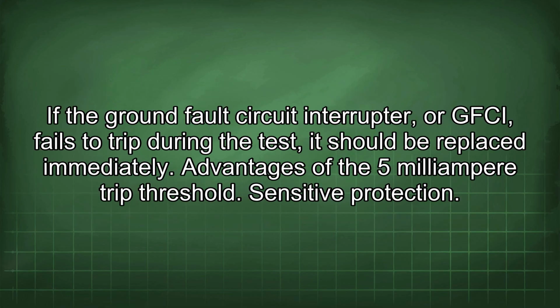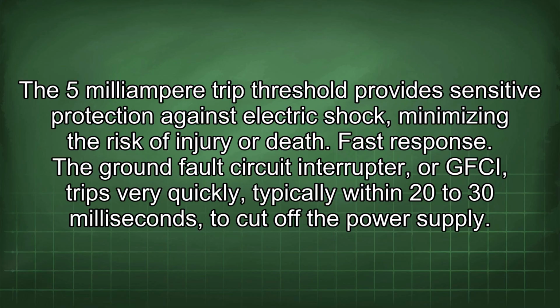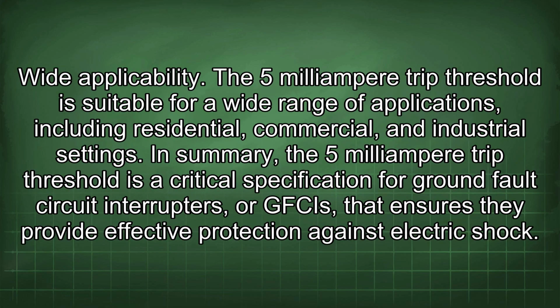If the ground fault circuit interrupter, or GFCI, fails to trip during the test, it should be replaced immediately. Advantages of the 5 mA trip threshold. Sensitive protection. The 5 mA trip threshold provides sensitive protection against electric shock, minimizing the risk of injury or death. Fast response. The GFCI trips very quickly, typically within 20 to 30 milliseconds, to cut off the power supply. Wide applicability.